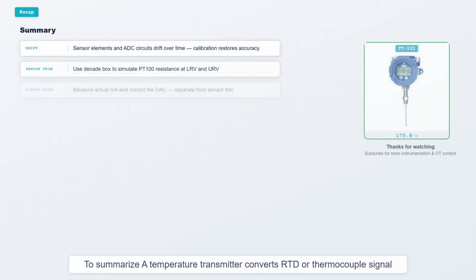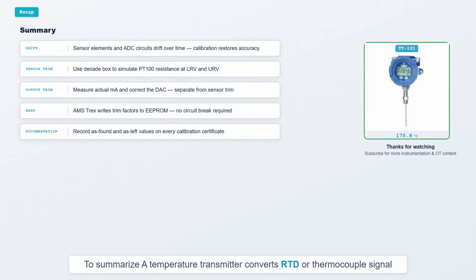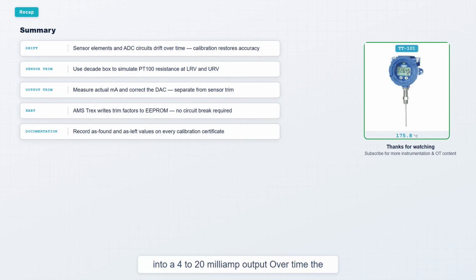To summarize, a temperature transmitter converts RTD or thermocouple signal into a 4 to 20 milliamp output. Over time, the sensor input and the analog output both drift. You correct sensor input errors with sensor trim using a decade resistance box to simulate exact PT100 resistance values. You correct output errors with DA trim, measuring the actual loop current with a calibrated milliamp meter. Smart transmitters store both trims permanently via HART. That 23-degree gap between your DCS and your local gauge? This procedure closes it.